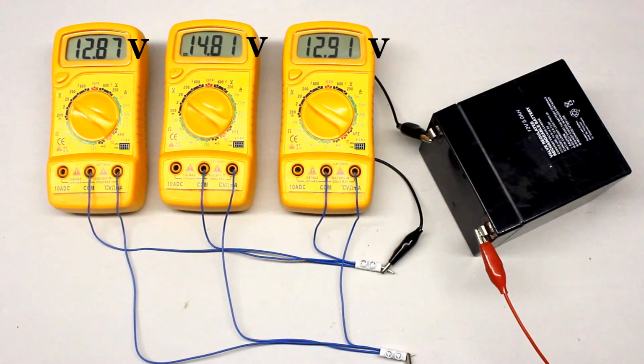After discovering measurement errors caused by the inner resistance of a multimeter, there is still one question. How reliable are the displayed values of a multimeter? Now all 3 multimeters are connected in parallel to a voltage source. The difference in potential applied to each pair of test leads is identical, hence all 3 devices should display the same reading. As you can see, they don't.